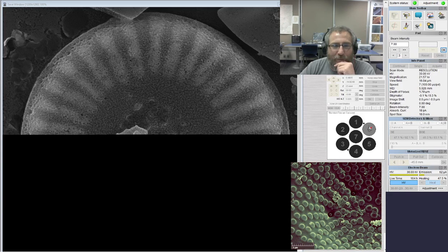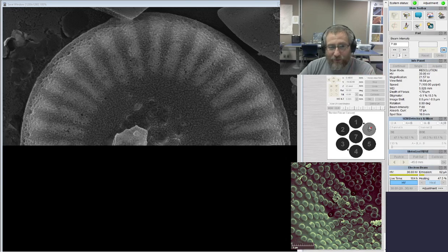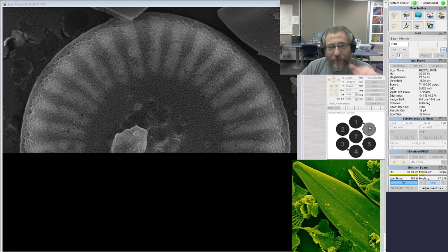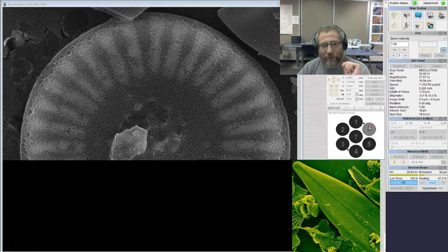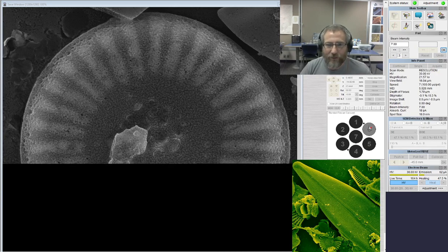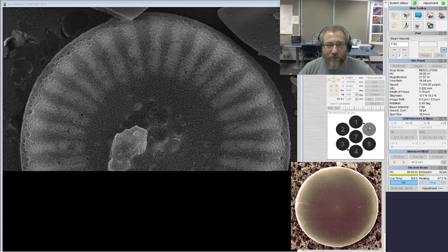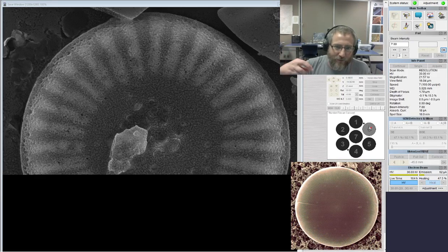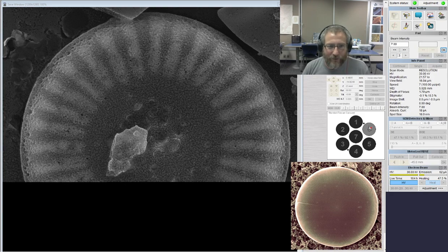If it were something made out of metal, you could just stick it straight into the SEM. You don't need to prepare it in any way. Or anything that really conducts electricity well. So it doesn't necessarily need to be metal. The whole idea of sputter coating, preparing the samples with gold, is to allow the electrons to discharge. We don't want them to accumulate on surfaces. The electron beam is hitting the sample, and the idea of sputter coating it with gold is to allow it to reach a ground more easily by being conductive.